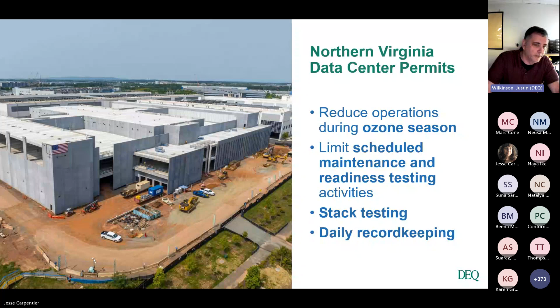Lastly, as we got more and more emission units at a facility, we used to have monthly rolling totals, but for data centers with that many emission units, they could operate 2 or 3 days for an emergency event and then exceed their annual emission limit. So we started looking at 365 rolling day totals, so they can identify potential exceedances much quicker than waiting for a full month to pass. Those are some additional things we've looked at and incorporated into our permits for data centers.